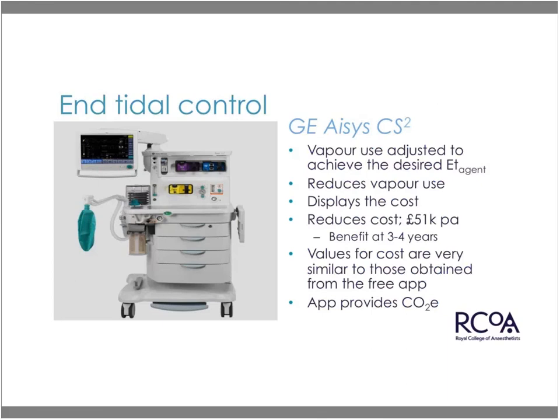We can only do what we've done with the help of the manufacturers, and this particular anaesthetic machine manufactured by GE has the capacity not to dial up and set the concentration that you want on the inspired mixture, but as I've alluded to already, this particular machine will dial up a concentration to achieve a specific end-tidal concentration.